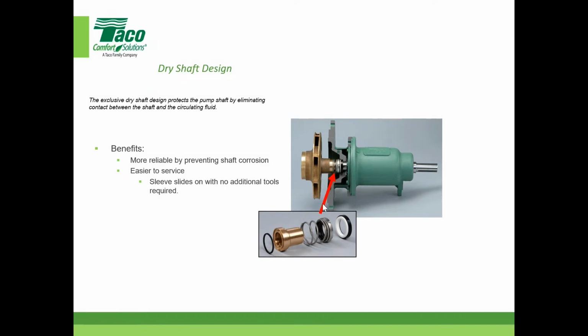So this is just a cutaway of the seal, this is the type of seal here. Our particular design has a dry shaft design, it prevents corrosion on the shaft, but you can see the components of the seal. Most pump manufacturers use a John Crane type of seal, pretty common out there. You've got to be very careful when you change these, if you smudge them up they're going to cause some issues for you.